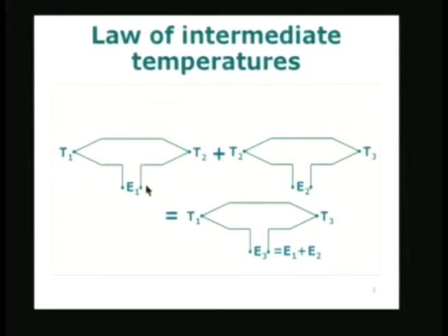Actually, what I should do is add this E1 to E2 to find out what is the output of this thermocouple if this were at the measuring junction temperature and this were the ice point. Therefore, to find out what is the correct temperature, all I have to do is to add whatever is going to be obtained by this arrangement between the room temperature and the ice point. This can be done by, of course, looking up a table.